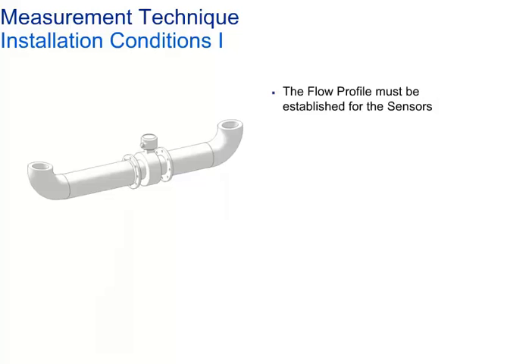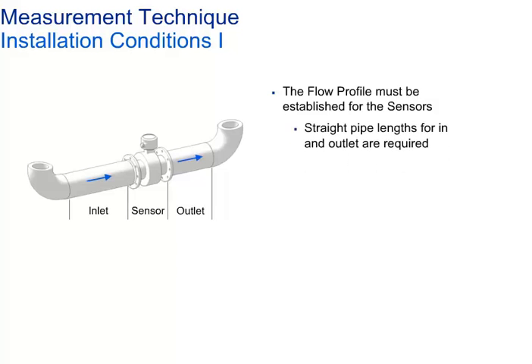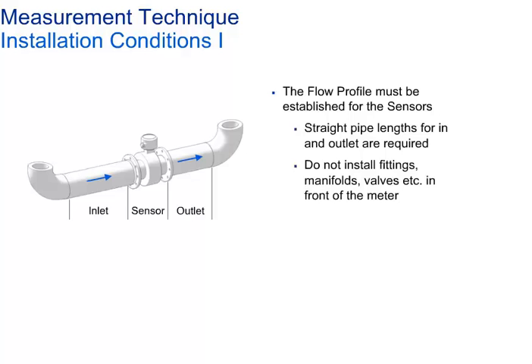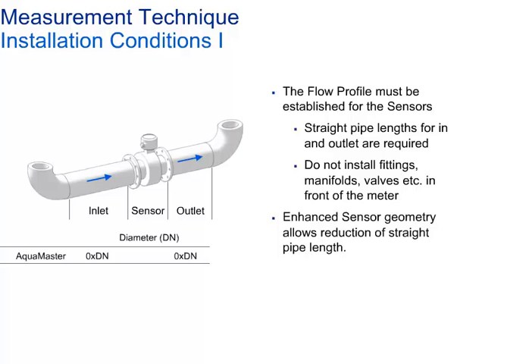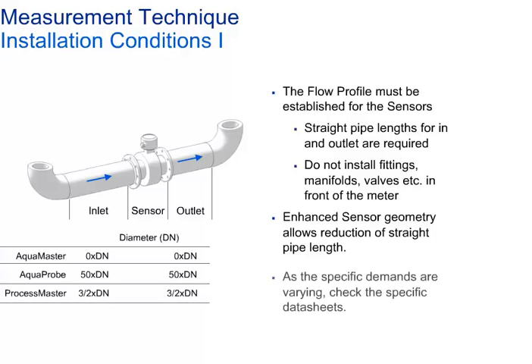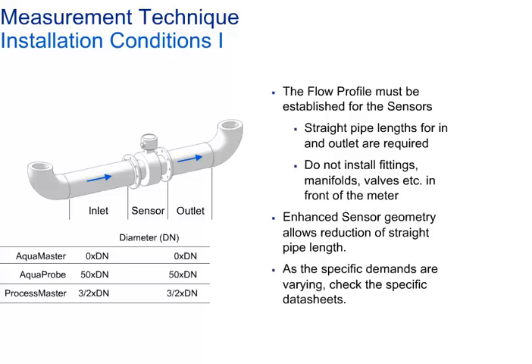The distribution of flow in different areas of the pipe should ideally be consistent. This distribution, known as a flow profile, is conditioned either by defined inlet and outlet straight pipe lengths or by using a special internal geometry for the sensor design. Do not install fittings, manifolds, valves, etc. in front of the meter tube, as they disturb the flow profile. ABB offers full bore, reduced bore, or octagonal sensor designs. Straight pipe length requirements range from 0×DN for the AquaMaster MMGA up to 50×DN for the AquaProbe. The ProcessMaster, for example, requires 3×DN upstream or 2×DN downstream.